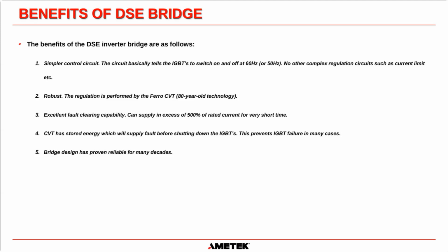Okay, so why have two technologies? That's a very good question. I'll explain the benefits of the DSE inverter bridge, which is the system that has the ferroresonant transformer in it, and then I'll do the same for DPP. The benefit of the DSE inverter bridge is that it's a simpler control circuit. The circuit basically tells the IGBTs to switch on and off at 60 hertz in North America, 50 hertz in some other places in the world. There are really no other complex regulation circuits such as current limit or voltage regulation. The control board is quite simply saying IGBTs turn on and off at 60 hertz. No other complex stuff whatsoever. The transformer does all of the complex regulation of the voltage and current limiting.